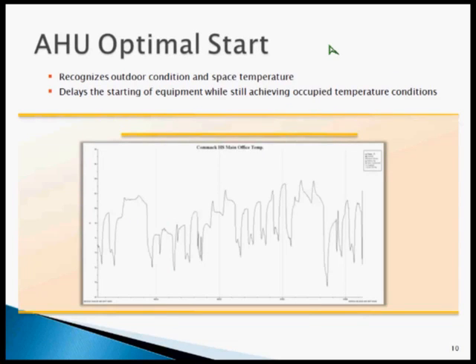What we're talking about is the response of the chilled water system, basically, in this case, but it could be any system, like an air handling unit. The chilled water system is serving air handling units all over the place. And this goes back to that example a couple notches before, where they added an air handling unit and it made them have to bring on 3 chillers. It's the same idea: look at your entire building, and make sure you're not turning on air handling units just because you are, even though there's nobody in there. In this school example, take an auditorium: nobody's in there, the hours go by, and there's not even anybody in there until 3 o'clock when it's time for choir practice, yet they're driving that air handling unit the entire time.